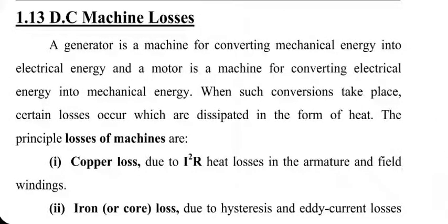A lot of these losses produce heat that has to be accounted for in designing the overall structure housing the machine. If the machine is getting too hot, you may have to think about providing sufficient cooling to it as well. Again, that is more critical when large powers are involved. The biggest contributor to heat is copper loss, for sure.